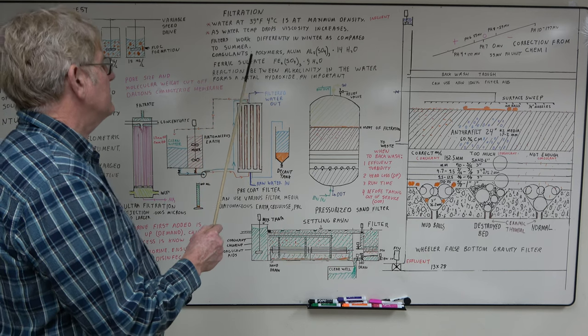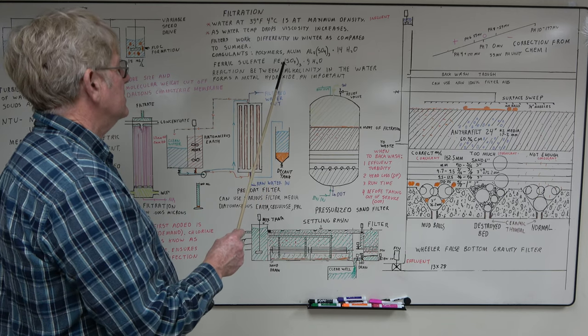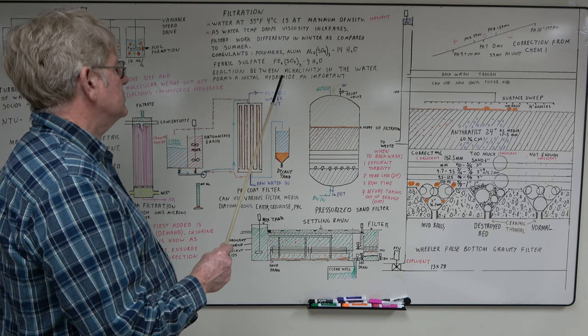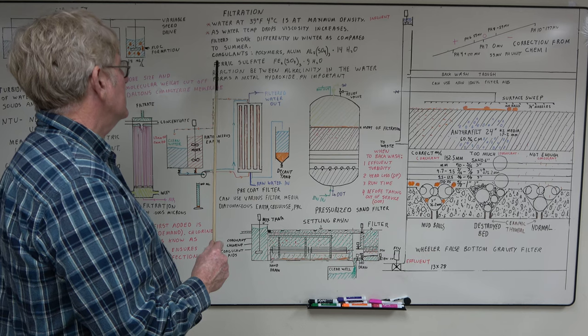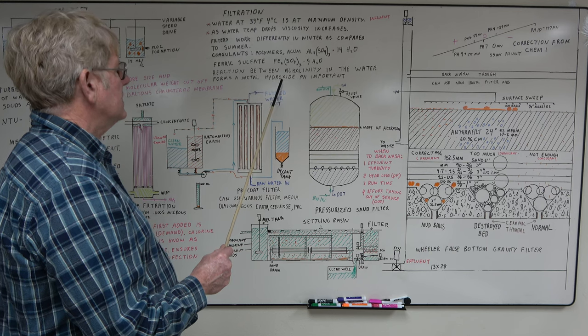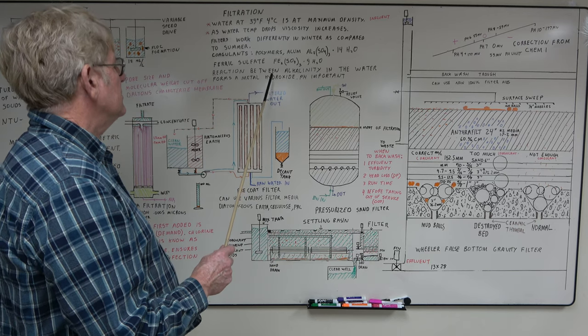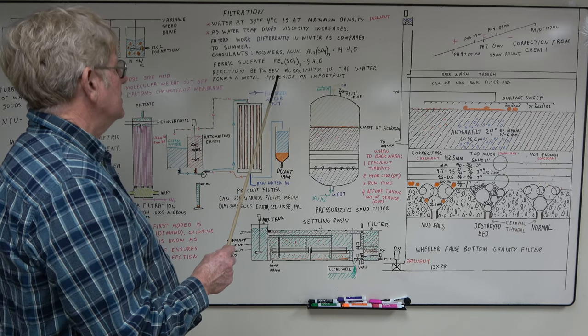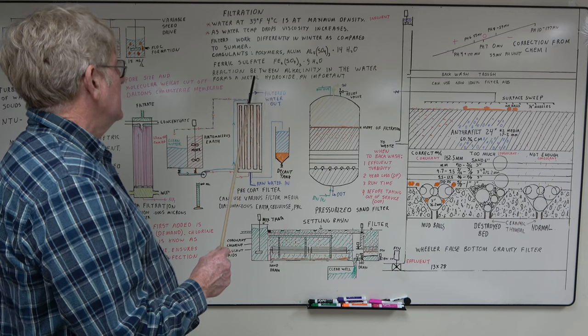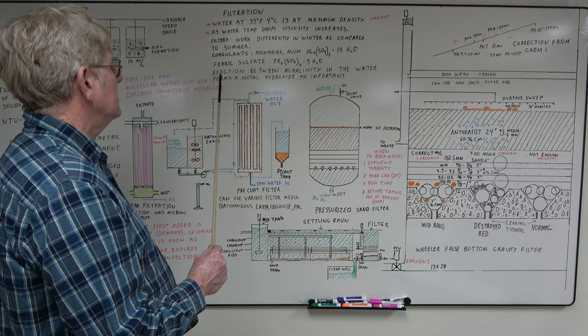Some of the coagulants used: they have synthetic polymers. Alum is the old standby, aluminum sulfate. Ferric sulfate works better in a little bit higher pH waters. The way the coagulants work: interaction between the alkalinity in the water and the coagulant forms a metal hydroxide. This creates a positive charge, and a lot of the suspended solids in the water are negative charge, so they'll stick together. They also will plate out on the particulate and make them stick together to form a floc. So the big thing with coagulants: they cause the suspended solids to stick together to form a floc which can be filtered better.